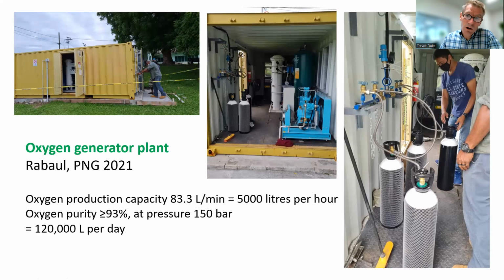Some oxygen generator plants can be transported in a container, such as this one. These again give an oxygen purity that's typically 93% or more, and this one, which can fit in a container, can generate 5,000 litres of oxygen per hour. So if you were to run it 24 hours a day, that's 120,000 litres per day. But realistically, most hospitals will have the technicians to run such a plant for 8 or 12 hours a day, maybe a bit longer, but it's still about 40,000 litres per day.